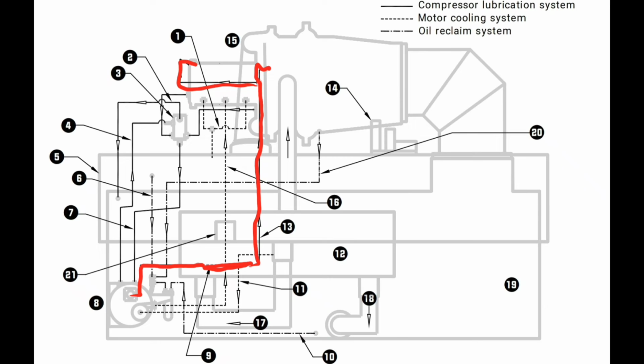So these machines, if I remember correctly, without checking the manual real quick, won't allow you to turn on until that oil is either 110 or 120. Anything below that, it will not allow you to function. I believe it's 120, that's what it is. So below 120 degrees, this machine is going to give you a low oil temperature indication, and it's going to be trying to run the oil heater until it gets above that.